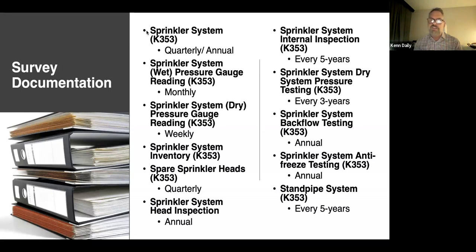And then once every 5 years, you have an internal inspection. Once every 3 years on a dry system, you have pressure testing. Then there's annual backflow testing. Every sprinkler system is required to have a backflow device on it to ensure that the sprinkler water would not back into your domestic system. And that testing is done on an annual basis.